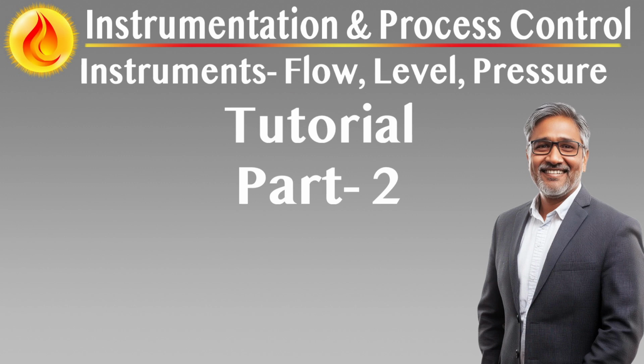Seal filling liquids must be process compatible and environment safe. Seal liquids must be selected in collaboration with the process design team and verified with the instrument vendor. Criteria include compatibility with process fluid in the event of diaphragm rupture, viscosity and thermal expansion properties over the full design temperature range, environmental and personnel safety in case of release, e.g. non-toxic, non-flammable, stability under vacuum or pressure transients, especially in wet leg level applications.